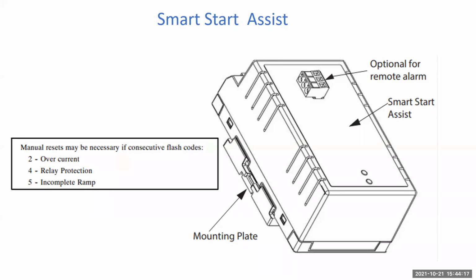The SSA reduces compressor starting currents and limits the peak, to keep the lights from dimming and stuff like that. They have a dedicated algorithm that's built in. We have no control over that. The SSAs will lock out. They'll incorporate their own 5-minute time delay. All this can also be found inside the service manuals.